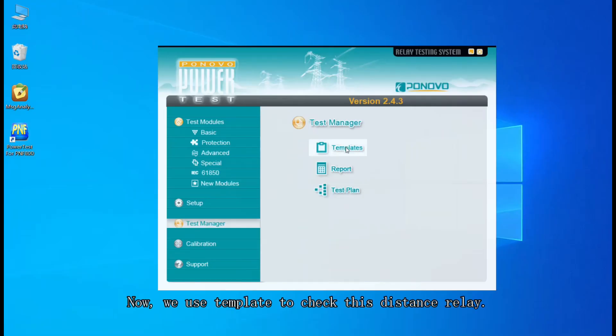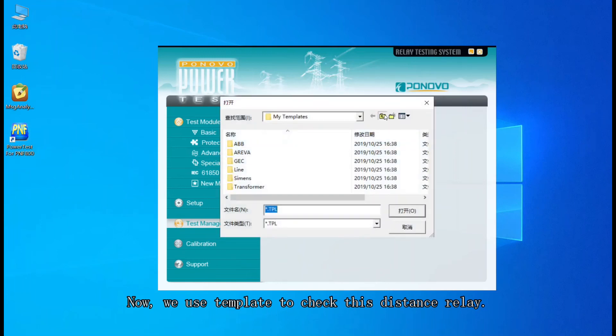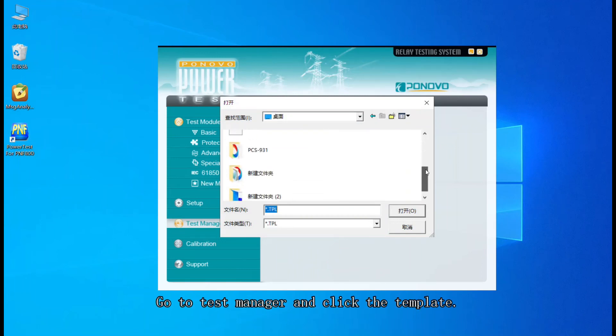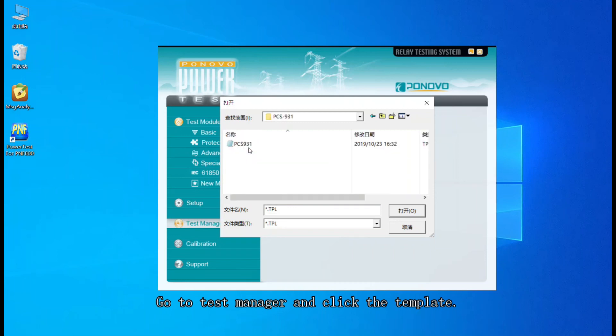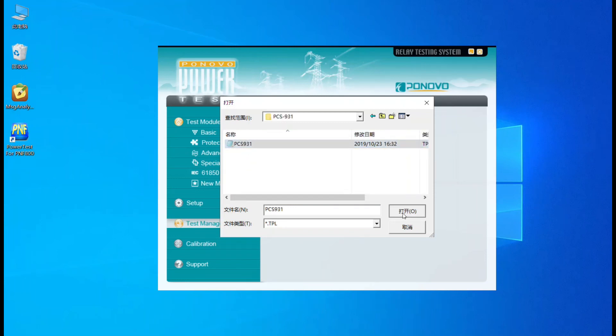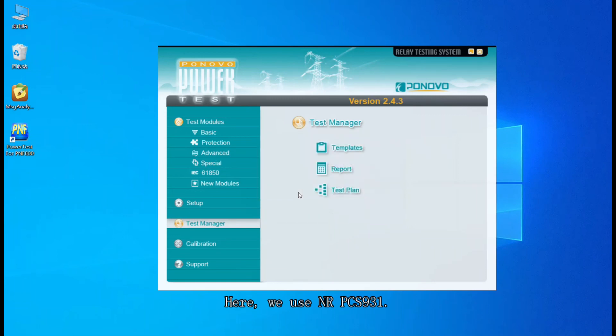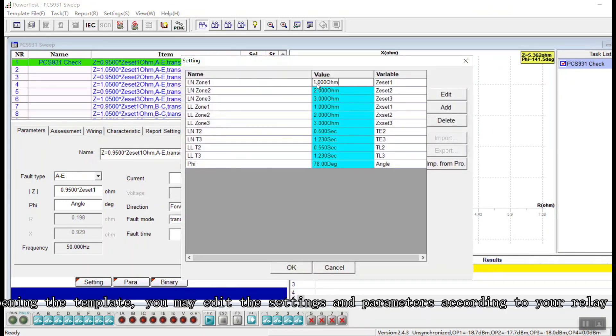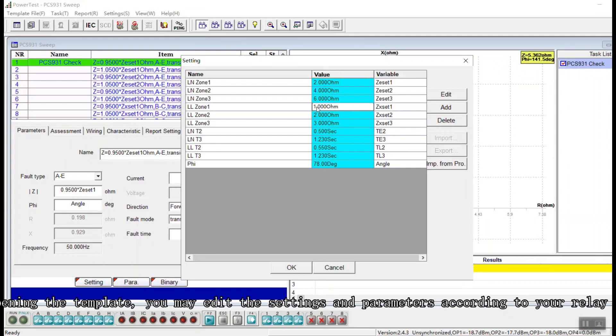The next part will use a template to test the distance relay. Go to Test Manager, click the template, and find the template you want to use. Here we are using PCS-931. After you open the template, you can change the settings, parameters, and everything according to your situation. In our situation, the zone settings are 2, 4, and 6.